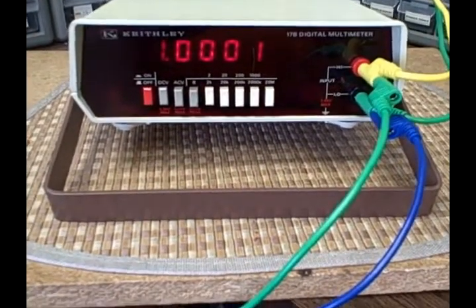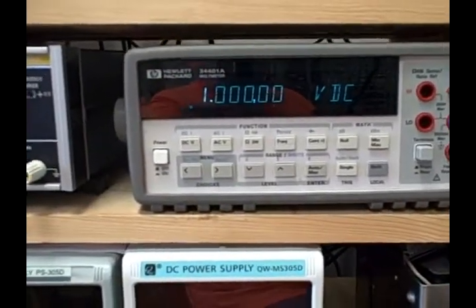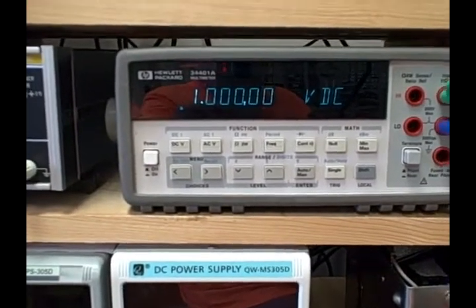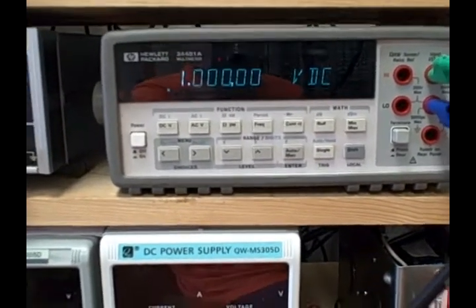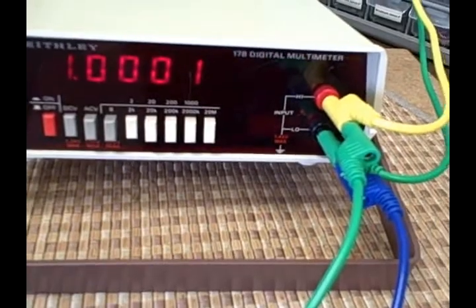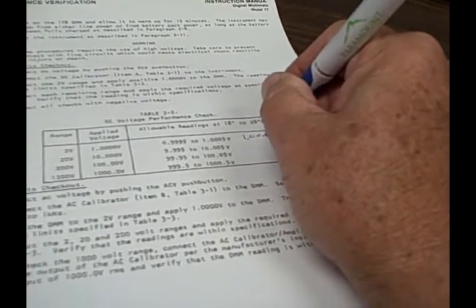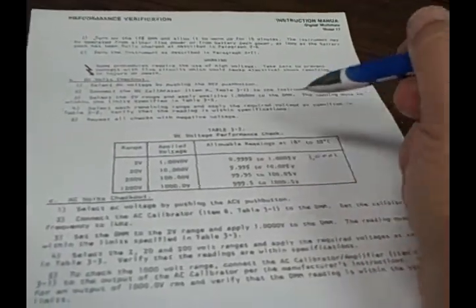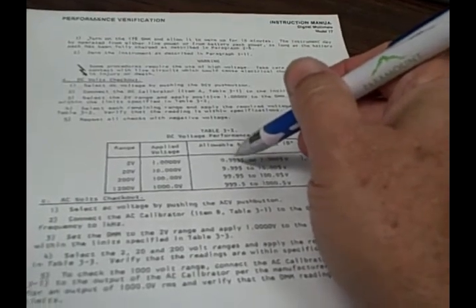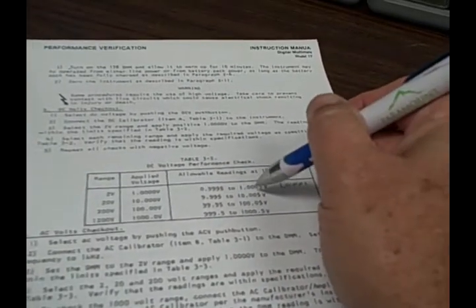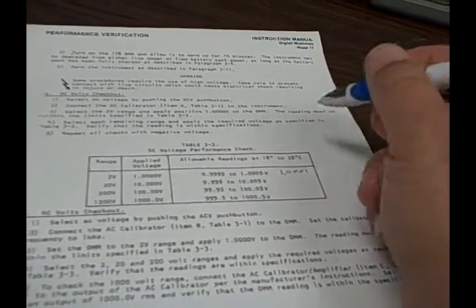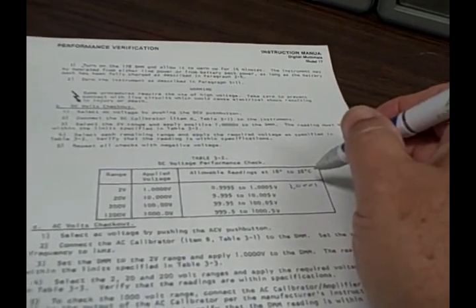Okay, we are on the 2 volt range DC input. We are reading 1.0000 volts DC on the Hewlett-Packard 34401. And we are getting a reading of 1.0001. Our readings are allowable and considered good if they're between 0.9995 to 1.0005. And we're 1.0001, so we're right in the middle.